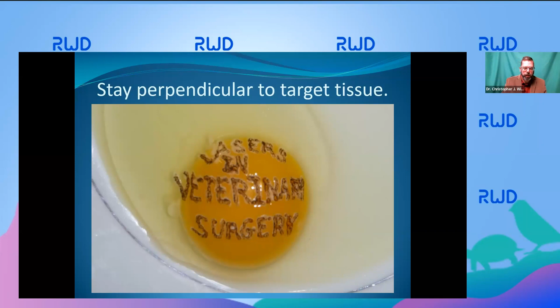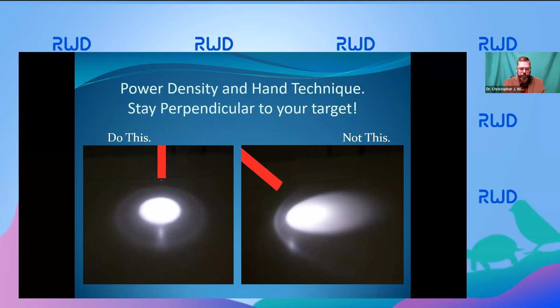So it's very important to maintain the distribution of power across the beam's geometry to keep your results consistent as you incise. Do this by keeping your handpiece as perpendicular as possible to your target tissue. This reduces the chances of reflection of the beam as well, increasing safety and maximizing the beam's efficiency for good results.